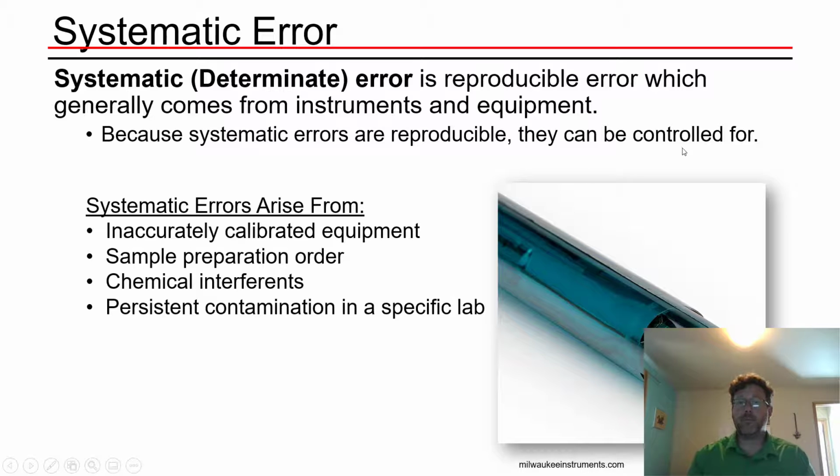So a specific example of systematic error would be if you have a pH probe and you calibrate it using a series of buffers at pH 4, 7, and 10, so that it will take accurate pH readings. If you calibrate it incorrectly at, say, pH 7, and you calibrate it to a buffer whose pH has slipped from 7 to 7.08, the pH probe will associate a current measurement that actually means pH of 7.08 with a pH of 7.